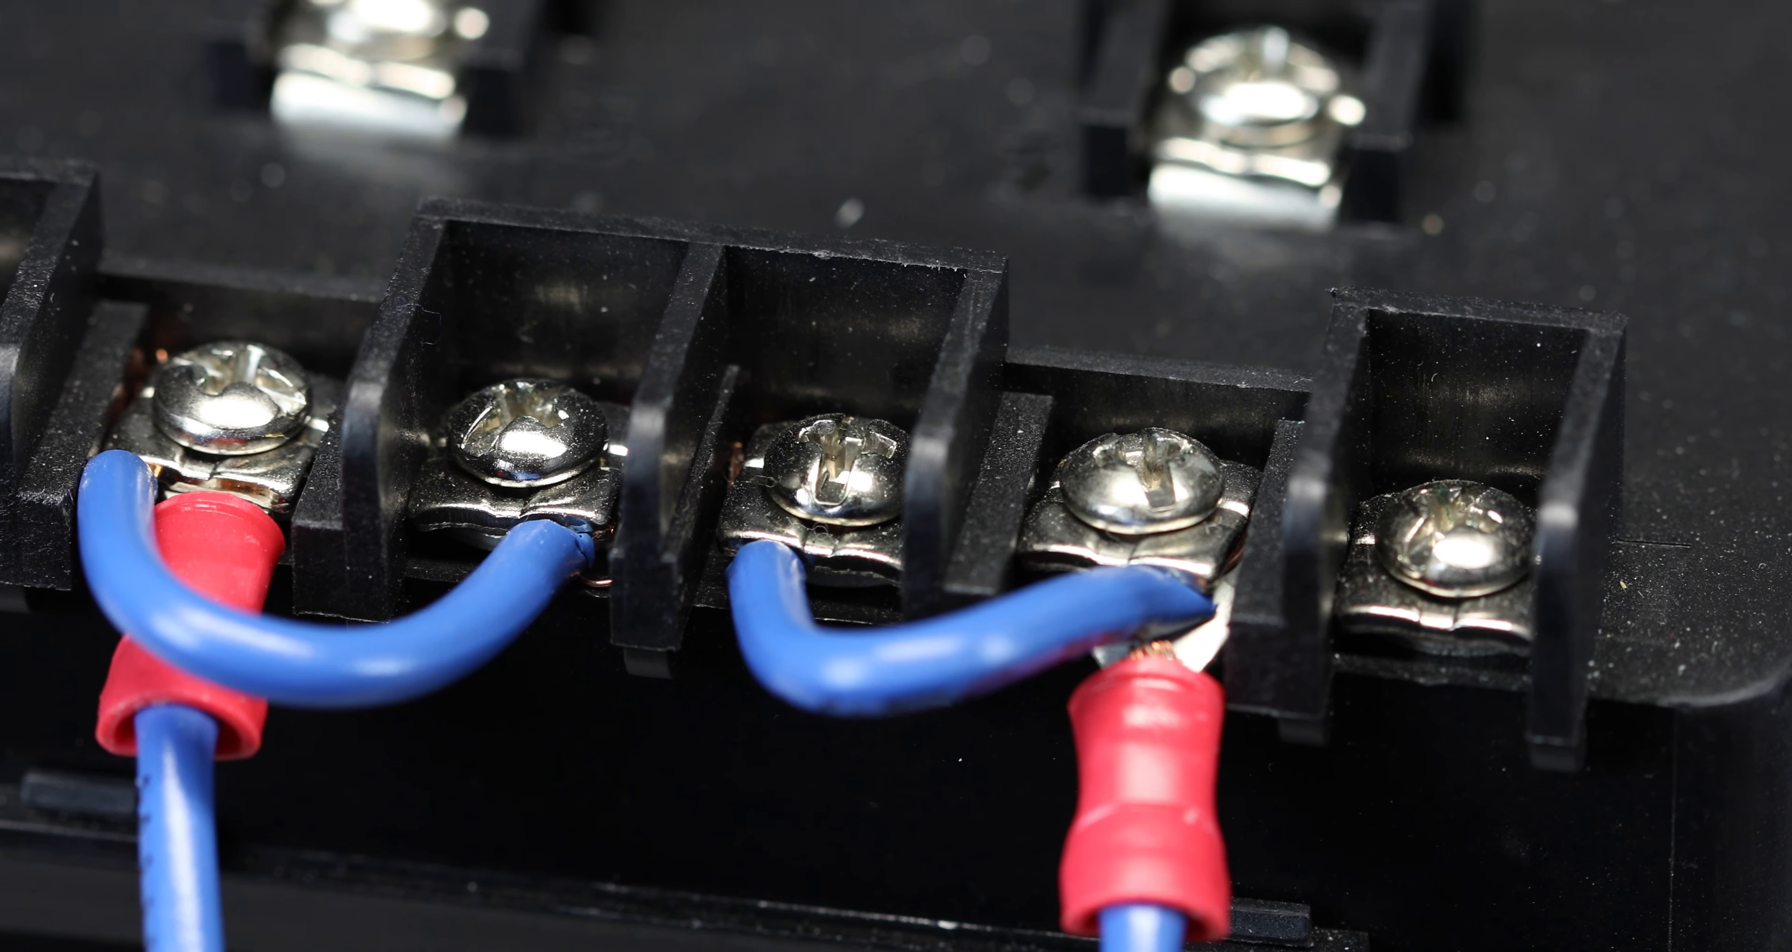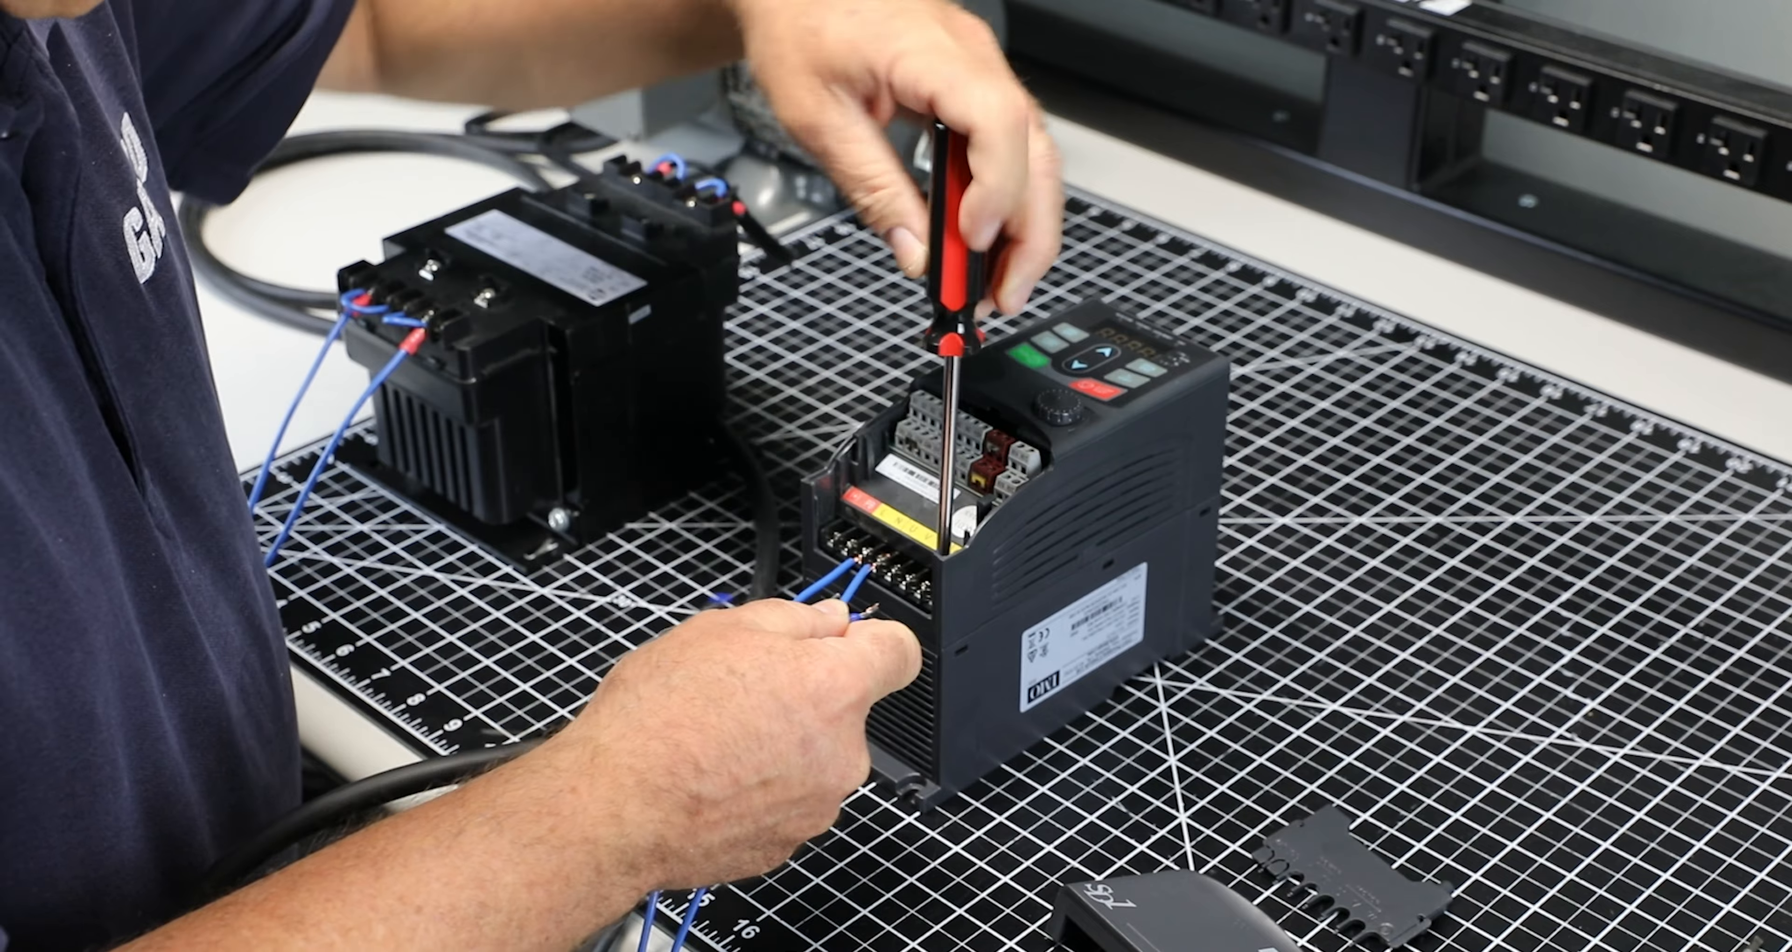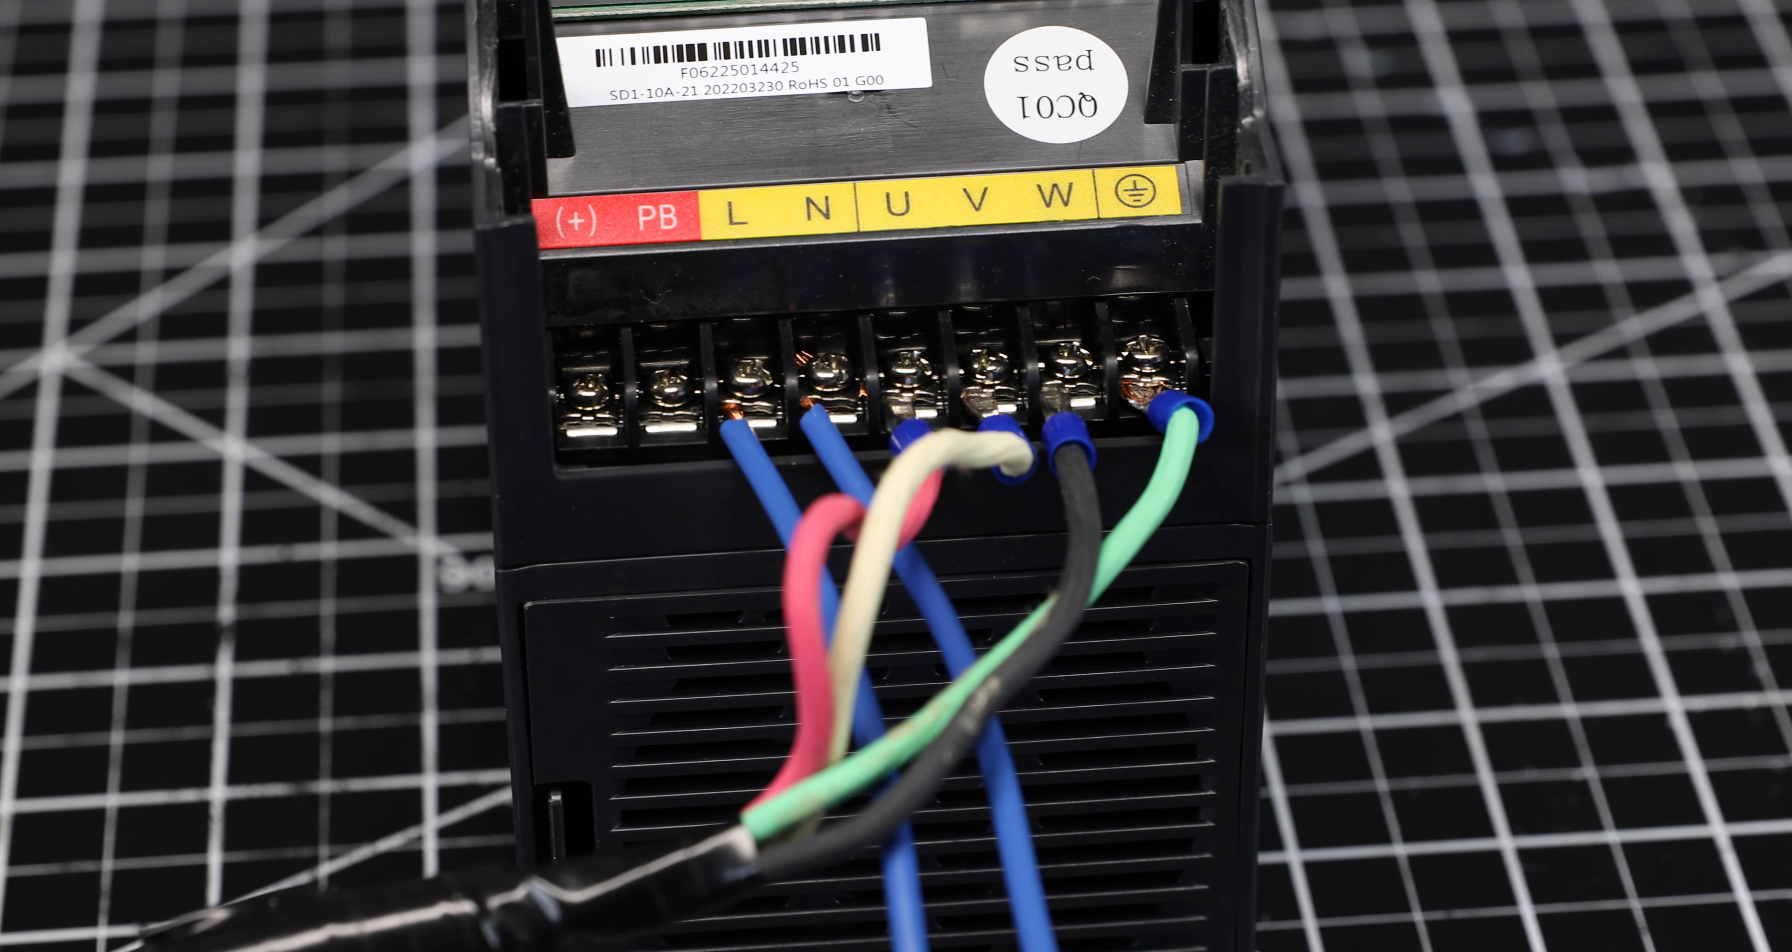Once the line power is connected, connect the output to the three phase motor. Connect the ground terminal, then connect the motor leads to terminals U, V, and W. Red to U, white to V, and black to W.